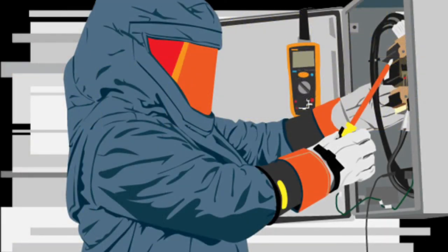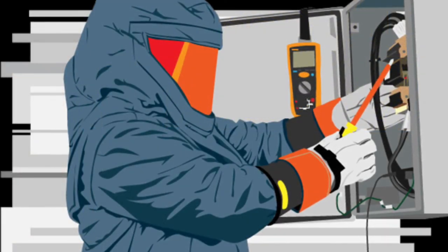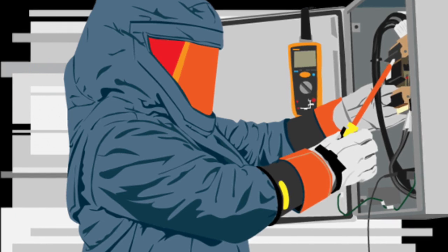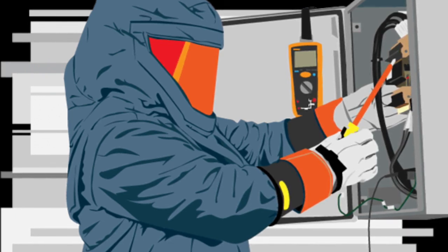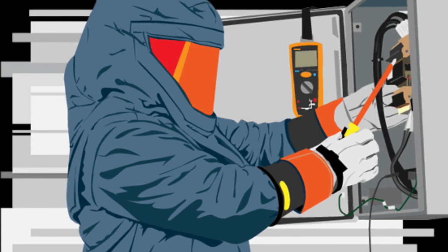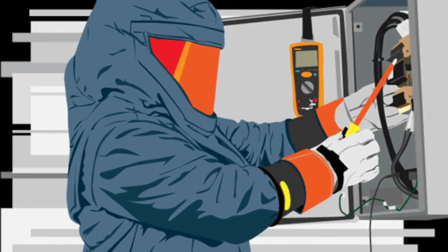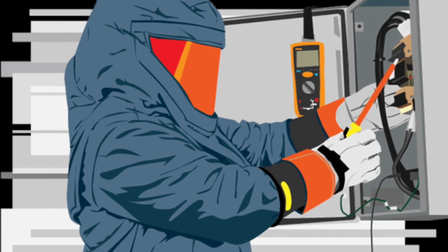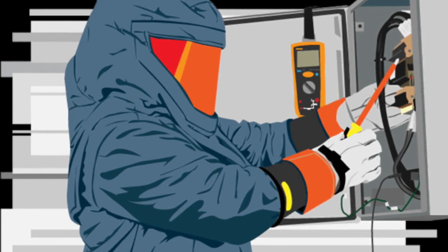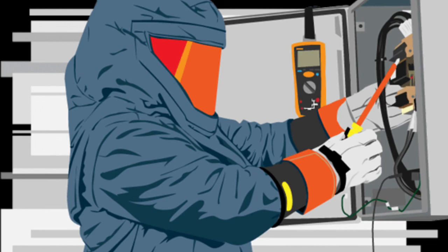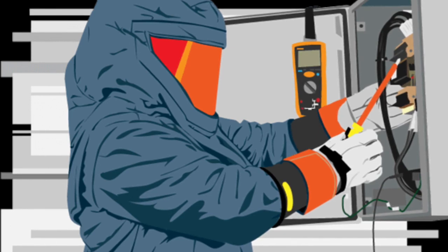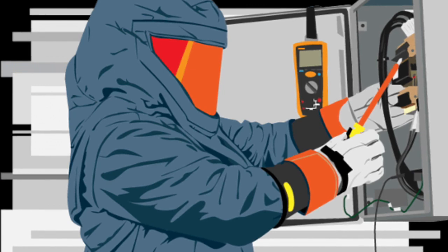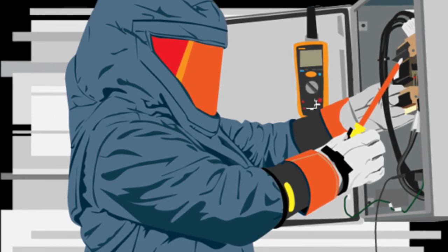Electrical safety program principles include inspecting and evaluating the electrical equipment; maintaining the electrical equipment's insulation and enclosure integrity; planning every job and documenting first-time procedures; de-energizing if possible; anticipating unexpected events; identifying electrical hazards and reducing the associated risk; protecting employees from shock, burn, blast, and other hazards; using the right tools for the job; assessing people's abilities; and auditing the principles.